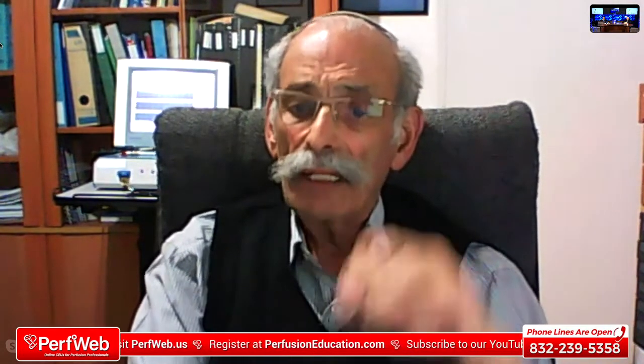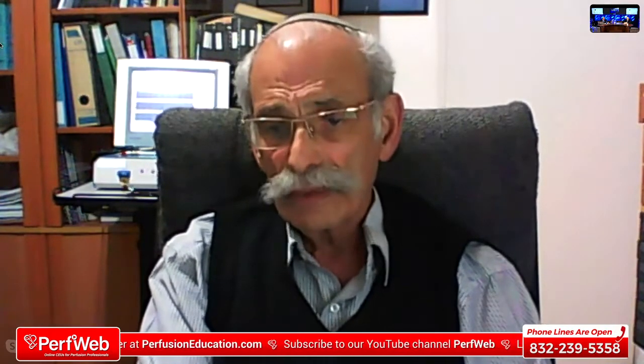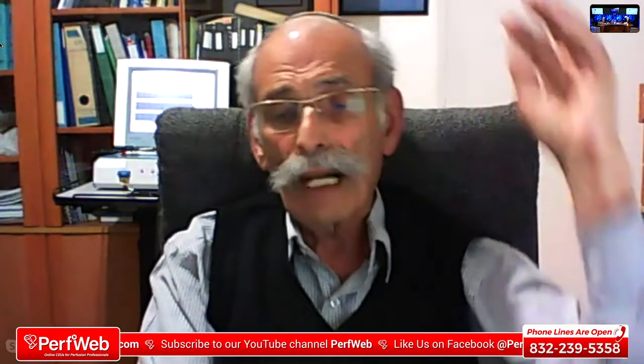Now, I have to mention that one of the wavelengths of light that we are using is a UV light for the monitoring of the mitochondria. And this penetration of the light is efficient enough only when you touch the tissue itself. So actually you are limited. You cannot do it from outside the body. You have to touch the tissue that you want to monitor. Unless it's a baby, in which case you can adapt to the skin.